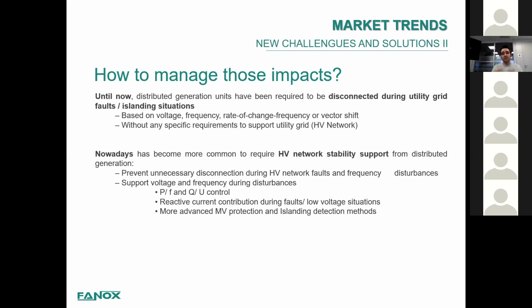However, nowadays, as the impact of these renewable energies is becoming bigger and bigger, they need to contribute to the stability of the system. For that, new protection and control schemes are required to prevent unnecessary disconnection during faults on the HV and MV networks, but also they have to be able to give support during this disturbance regarding voltage and frequency, and injection of reactive power. So these control schemes need to be much more complex, and they need to take into account not only voltage and frequency, but also power, the active power and reactive power, and mix them with the control of voltages and frequencies.